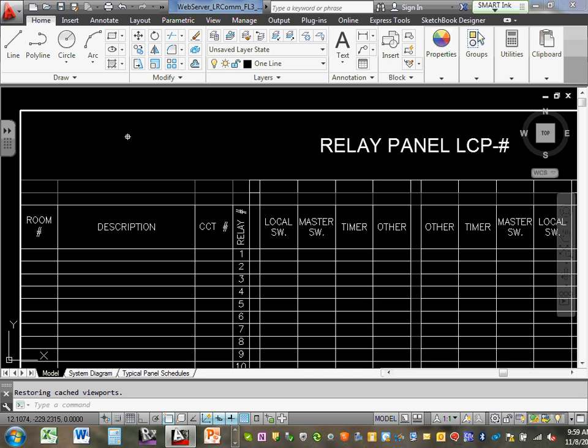Then timer functionality or other functionality. Timer functionality tells me whether or not we're going to tie it back to a time clock and use astronomical controls, or all of those other things that we can use to trip it, whether we're doing time control with daylight sensing, or occupancy sensing. So we give this to the engineers as a template, just as something they can expand. They can make as many columns as they want, because the control is going to get more and more granular as time goes on. So it's a good place to start. It helps you logically break things down.